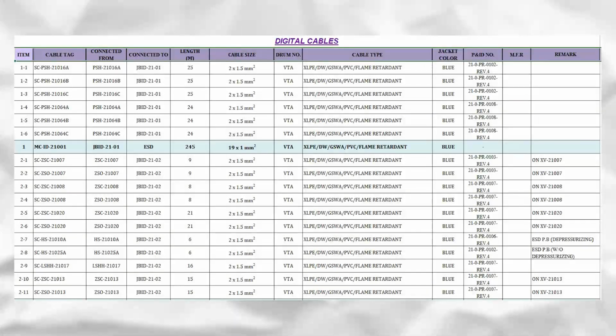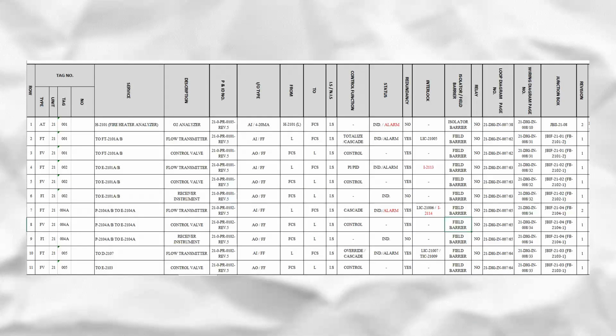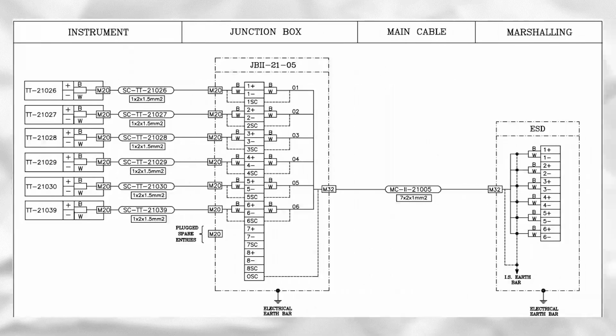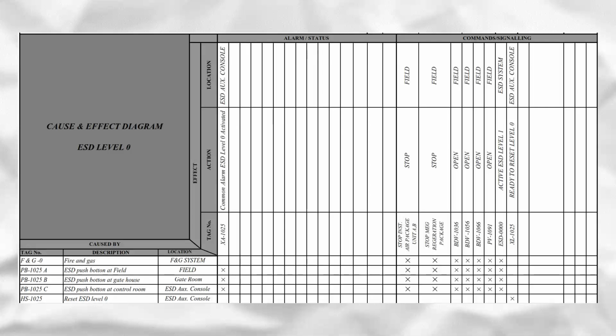Cable list is a document in which all cables laid in a project are specified. I/O list, which is the most important document to design a control system, is prepared to show how many input and output signals exist in a project. Wiring and termination diagram is a construction type document in which the connection of each field instrument with a related junction box is drawn. Cause and effect matrix is a document in which the effects of the group of signals on others are marked.